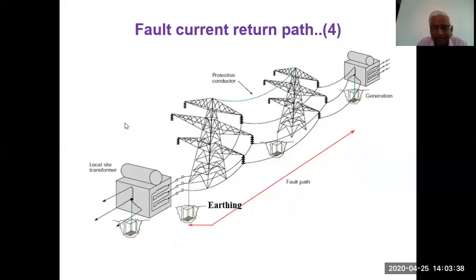Now take a case of a fault current return path. Is there any return path, directly or indirectly? You see, this is the generator given, and two towers have been shown here, and the last one is a local transformer again. The local transformer is a delta transformer, and the supply transformer is a star transformer. The neutral of the star is also grounded. So whenever there is a fault here, and the tower is also grounded, the current goes back to the supply through this earth. On top of the tower there is a protection conductor. It goes through the protection conductor, again through the tower to the ground, and goes back to the system. So it is a closed loop.